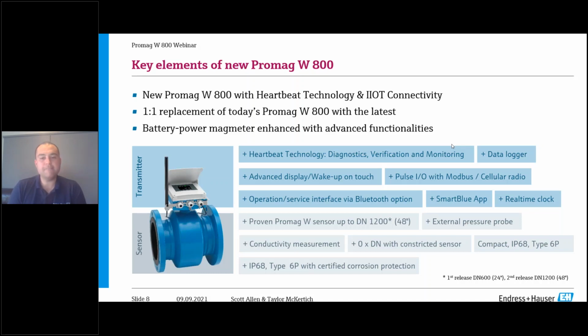We have large varied pipe sizes, up to 1200 will eventually be available. There's an external pressure sensor, not integral to the meter mounted through the spool piece of the tube, but an external sensor. It can be installed in the line up or downstream of the Flowmeter, with wiring running back to the Flowmeter. The Flowmeter powers the sensor, and the pressure measurement is made available for output, be it on Modbus or via radio.